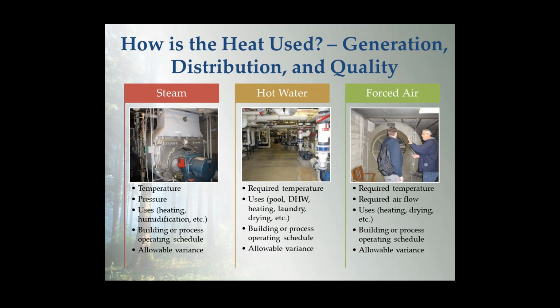Energy can be used in a lot of different ways. Heat energy, thermal energy in a system. The existing system may be a steam system, and that steam is developed at different pressures and different temperatures. It can be used for heating, humidification, process energy. We need to know what the operating schedule is and what the range of pressures and temperatures required in the system is, so that we can determine how we can meet those same requirements using wood.